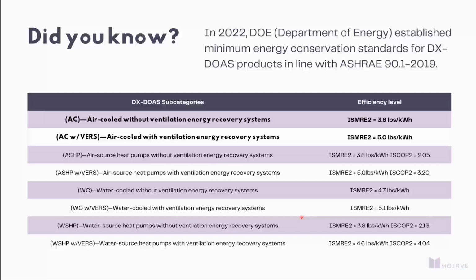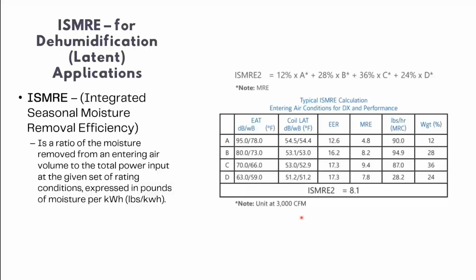Regardless of local and state codes, though, at a federal level, if any DOAS manufacturer or dehumidification manufacturer wants to sell product in the United States, you have to comply with these federal minimums. What does this actually look like calculation-wise? It's a weighted metric, very similar to IEER, focused on higher latent points and how efficiently you're pulling moisture out at a defined set of points. And the intent here was really to provide the consulting community and owner community an apples to apples way of comparing one dehumidification product to the next, to the next, to the next.